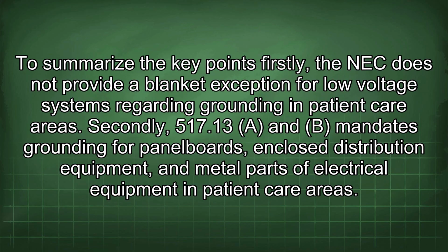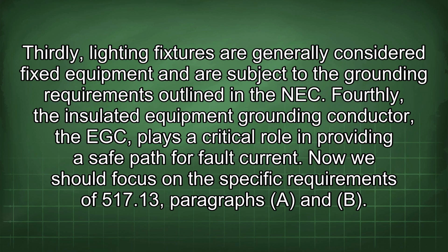To summarize the key points, firstly, the NEC does not provide a blanket exception for low-voltage systems regarding grounding in patient care areas. Secondly, 517.13 A and B mandates grounding for panelboards, enclosed distribution equipment, and metal parts of electrical equipment in patient care areas. Thirdly, lighting fixtures are generally considered fixed equipment and are subject to the grounding requirements outlined in the NEC.